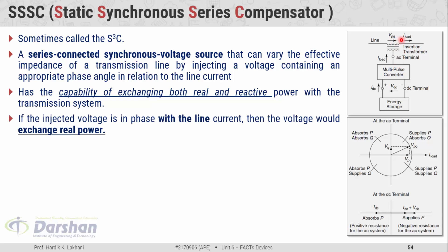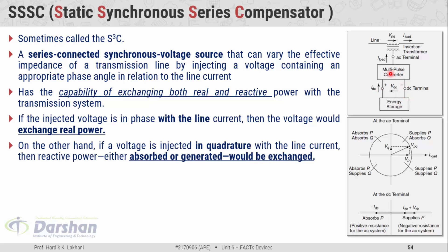If the injected voltage VPQ is in phase with the line current, then real power exchange would happen between the line and the compensator. On the other hand, if the injected voltage is in quadrature with the line current, then reactive power is either absorbed or generated. In short, the phase angle of the injected voltage decides either the exchange of real power or reactive power.